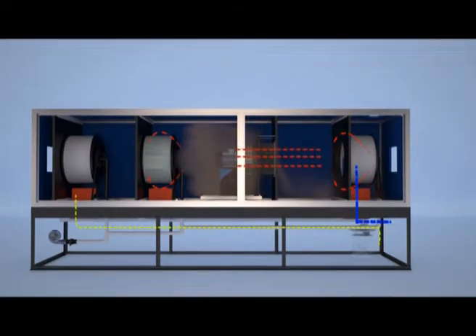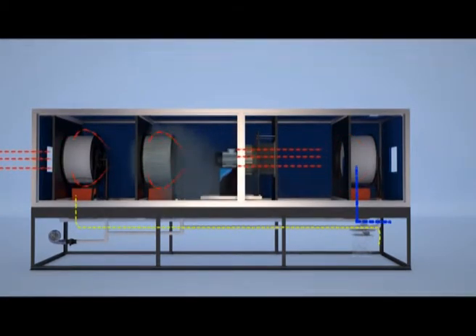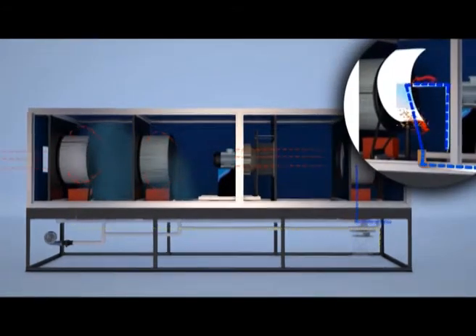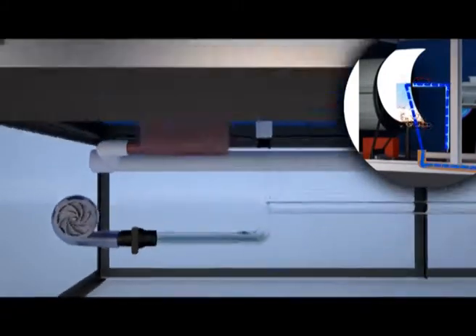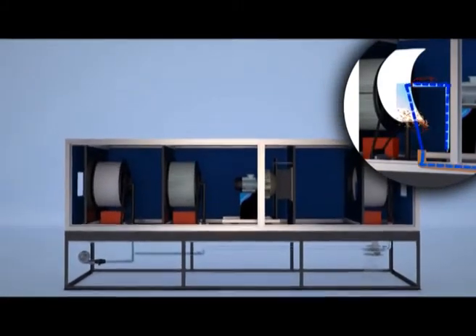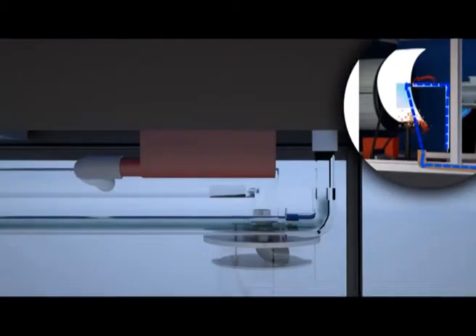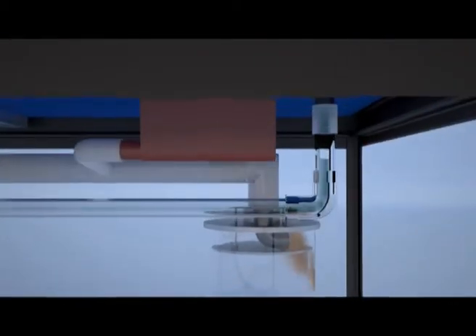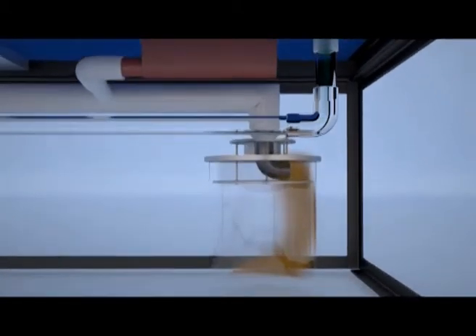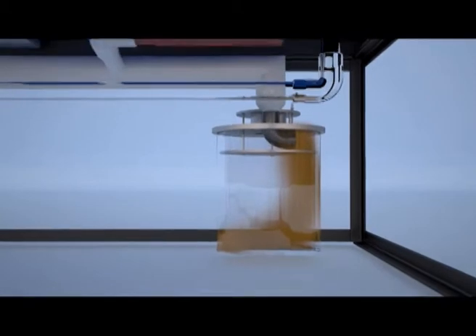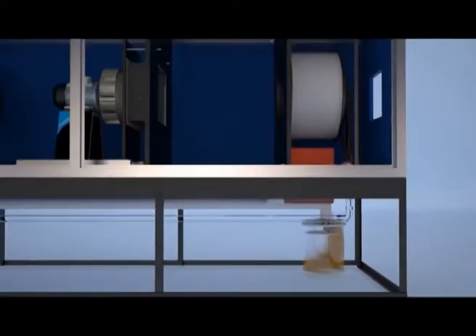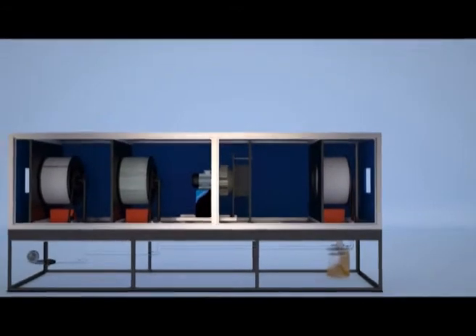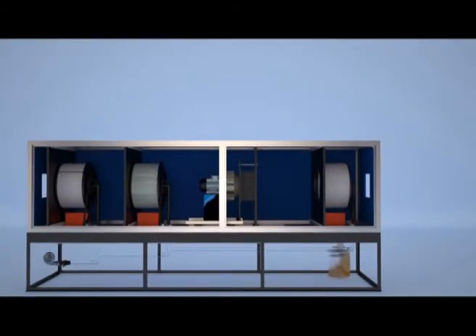The dust particles remain on the outer side of the periphery of the filters, which rotate and come to the downside. There is a provision inside the filter to blow off filtered air by a blower at precise velocity and precise pressure. On the bottom of the AHU, we provide a suction point which is connected to the pulse jet dust collector. The dust collector sucks dust from the air that parted from the filter. No dust particle remains in the AHU and the filter is continuously free from any dust particle. Thus the system remains clear and the AHU remains totally clean.